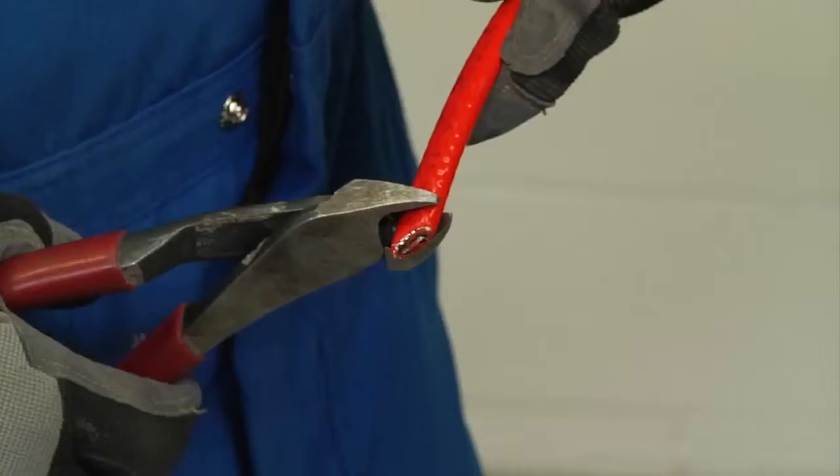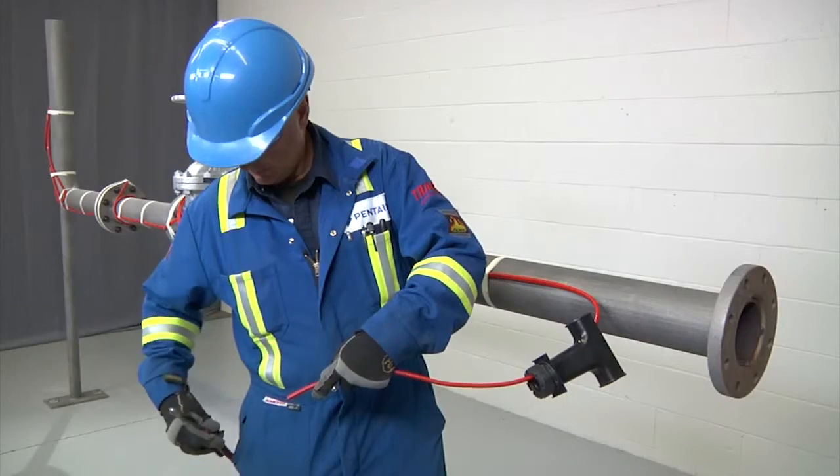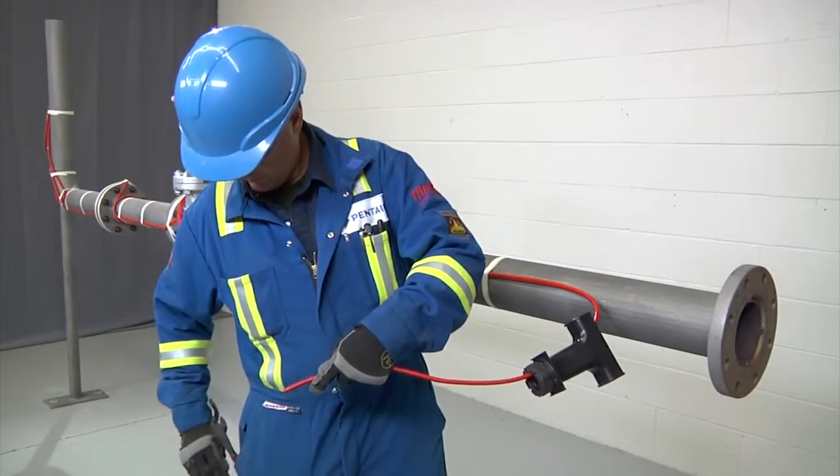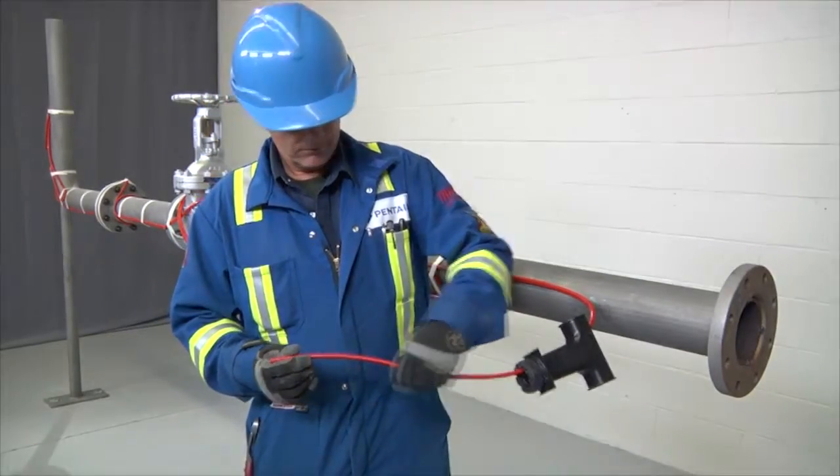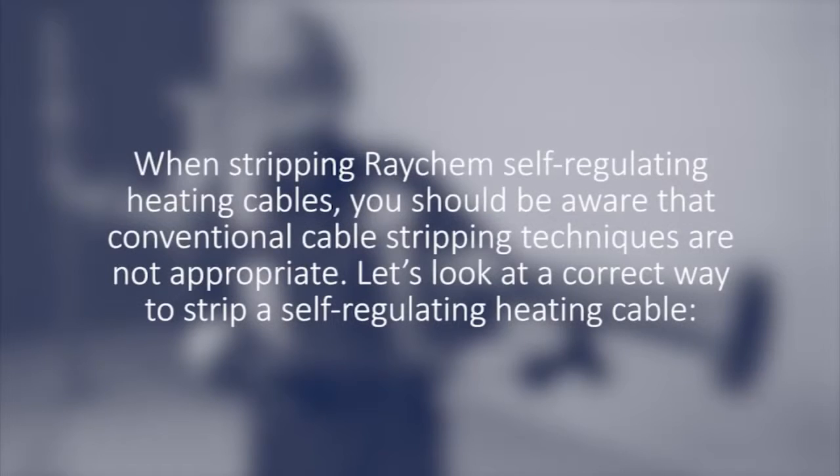Square off the cable end with a 90-degree cut, but do not attach to the pipe yet, and proceed to stripping the end of the cable. When stripping Raychem self-regulating heating cables, be aware that conventional cable stripping techniques are not appropriate. Let's look at the correct way to strip a self-regulating heating cable.